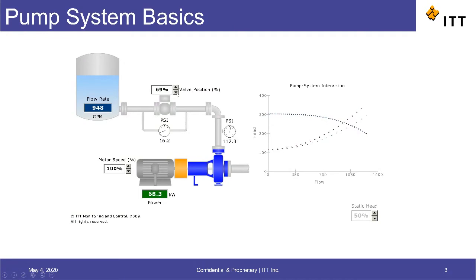So as the valve is closed, it essentially changes the shape of the system curve until it intersects with the pump curve close to our desired flow rate of 700 gallons per minute.